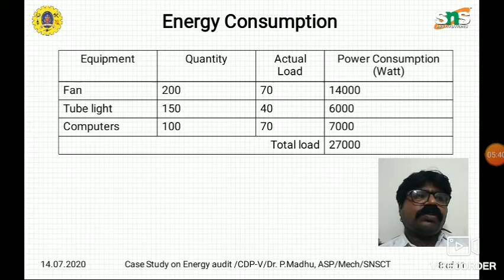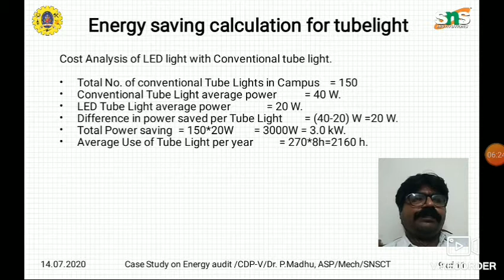In our case, we are considering only the tube lights for the energy auditing. Suppose we are using 150 conventional tube lights, each consuming 40 watts. If we replace them with 20 watt LED tube lights, we save 20 watts per tube light, so for 150 tube lights the saving is 3 kilowatts. The average use of the tube light per year is 270 days at 8 hours, so totally 2160 hours. So the energy saved per year is 3 into 2160 kilowatt hours, so almost 6,480 units of power we can save.